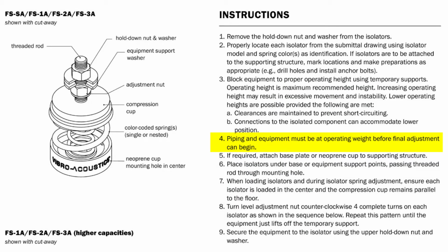This is to ensure the pipe and equipment doesn't move much when the additional weight of water is added to the system. Any movement can add stresses to the pipe which can cause problems. With isolated inertia bases, this means that the shims shouldn't be removed until after the system is filled and the springs adjusted. As stated here, it is important that the isolators are positioned so that the load is in the center and the compression cup stays parallel to the floor, keeping the spring vertical and not bending over, which in extreme cases could lead to failure.